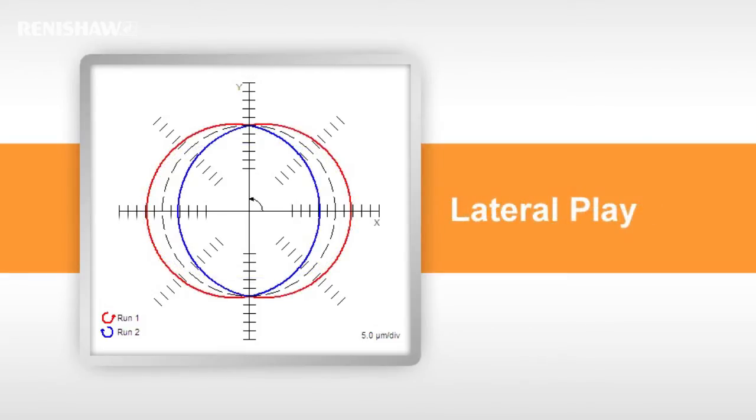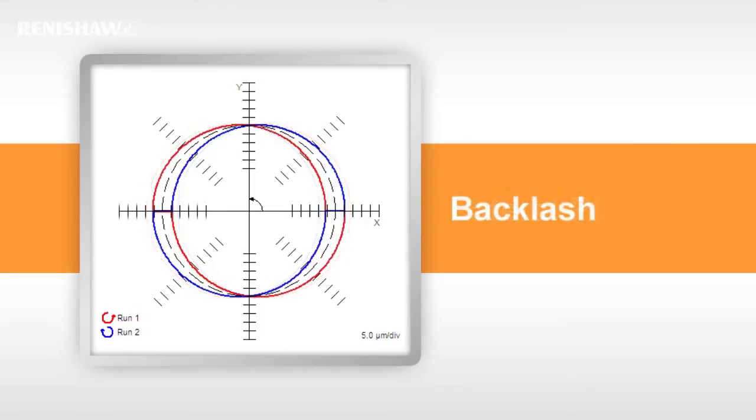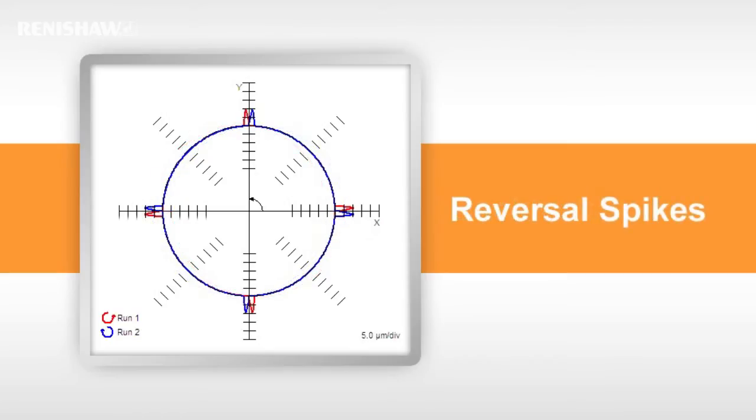Lateral play or slot. If clockwise and counterclockwise runs are displayed, one plot will appear inside the other. Backlash appears as a step towards the centre of the plot and the affected axis. Reversal spikes appear as short spikes aligned to the axis.